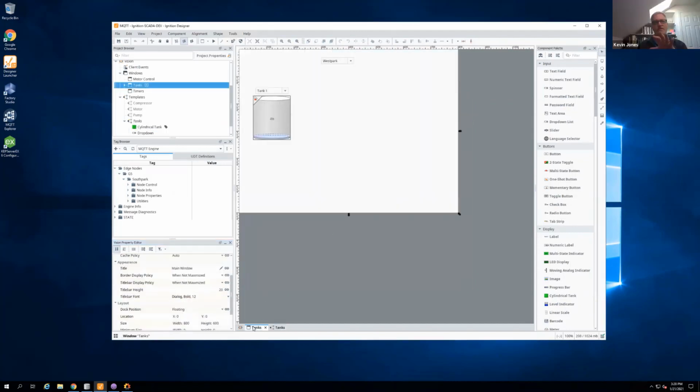And to be clear too, that unified namespace, that naming convention you had defined, is the convention that comes from ISA 95. Again, it's the ISA 95, exactly. So it's enterprise, site, unit, line, cell. And that's how you want to follow that all the way through.